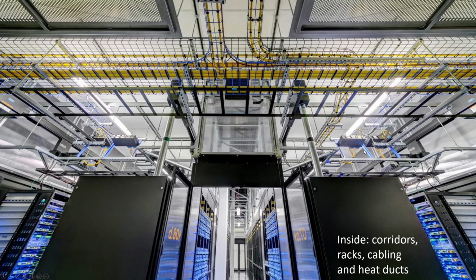We've seen this picture before, but I wanted to bring it back to show the chimney. If you look carefully, this is a hot aisle, and these are cold aisles. The hot aisle has this glass structure on top of the rack. Hot air comes out of the servers from both sides, and it doesn't have anywhere to go but up, so it rises without mixing in with the rest of the data center, going straight out through the ceiling. This drives the hot air out of the data center.